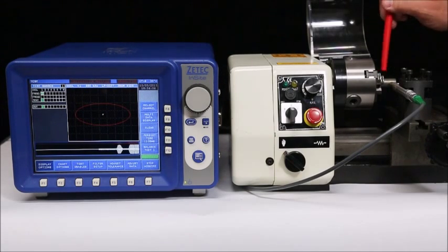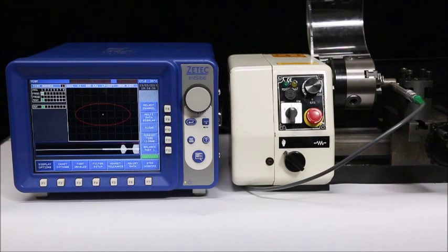On the roller bearing standard I have in the lathe here, there is an EDM notch of two thousandths of an inch in width, two thousandths of an inch in depth, and one hundred twenty thousandths of an inch in length. I have a probe connected with a surface liftoff distance of fifteen thousandths of an inch.